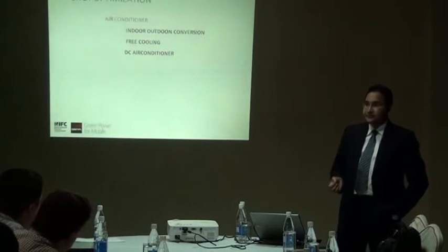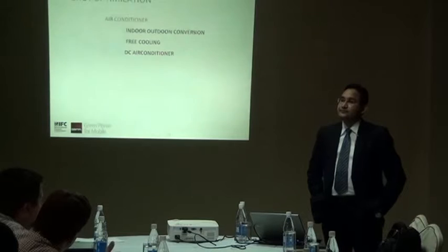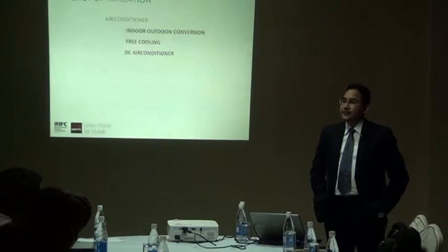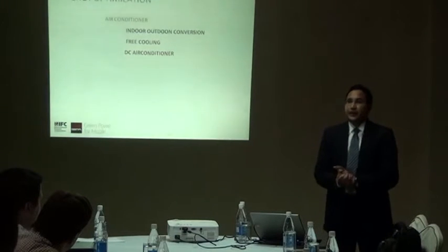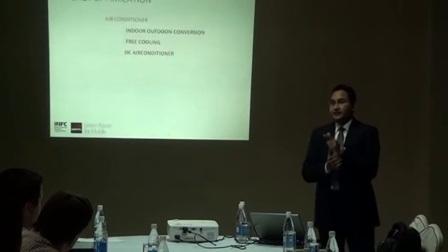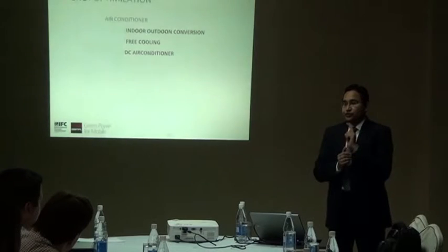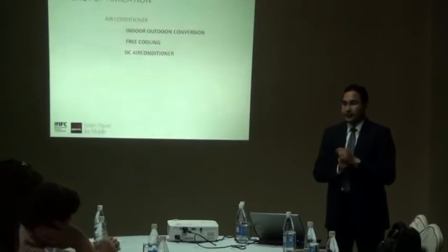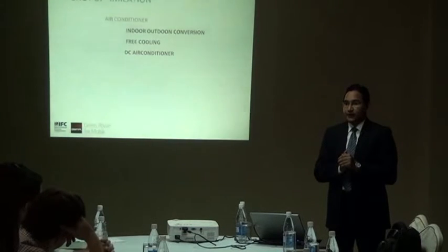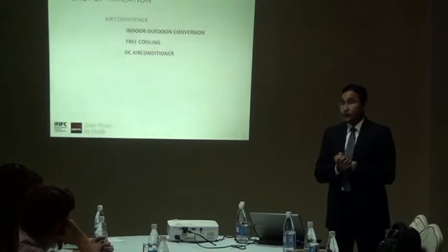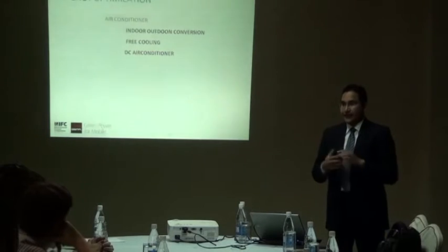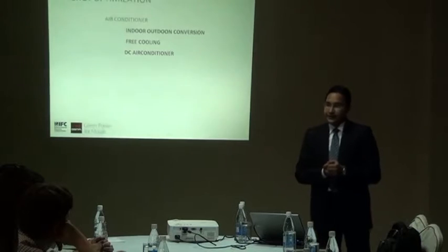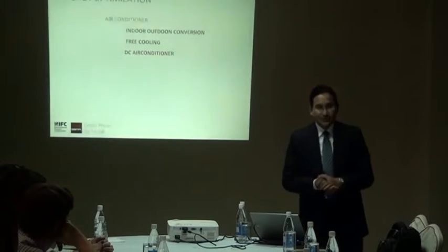If you refer to poor grid, is it blackout or brownout conditions typically that you look at? If I understood the question correctly, what we are defining as a poor grid is a site where the grid unavailability is more than 12 hours a day. So if a site is not having grid for more than 12 hours a day, it's a poor grid site.